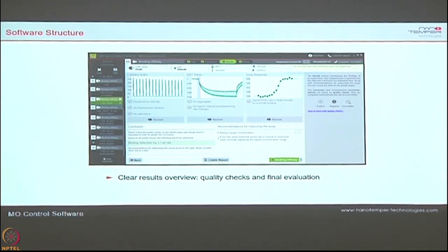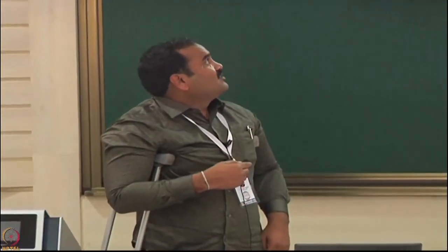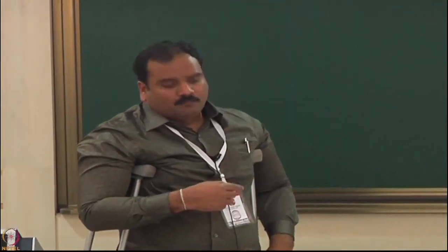If you are not getting proper results for any reason, the software will automatically give you suggestions. If this is not a binding fit, it will tell you to change the buffer, change the pH, or change the protein concentrations. Like this, the software automatically does the assessment. As a user you can always assess technically by looking at the data, but the software helps you make a judgment. All data is displayed in a single page — here is a clean binding fit, with all the thermophoretic traces of all your dilutions.